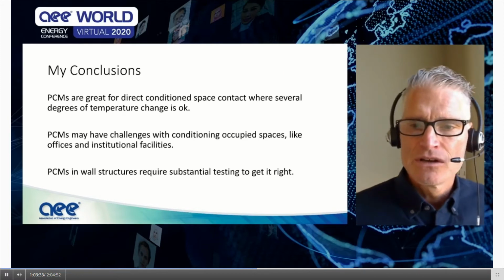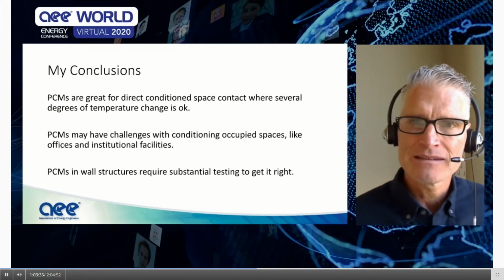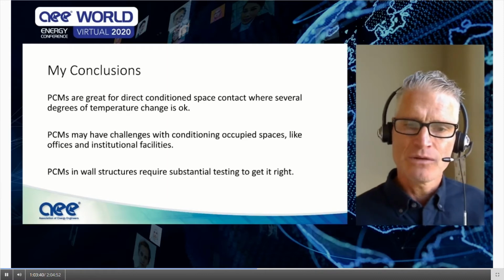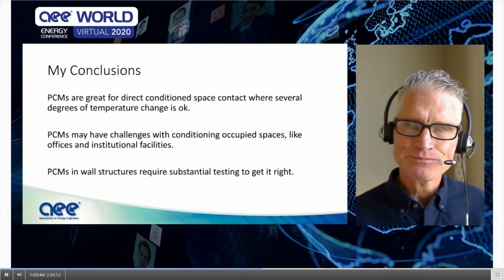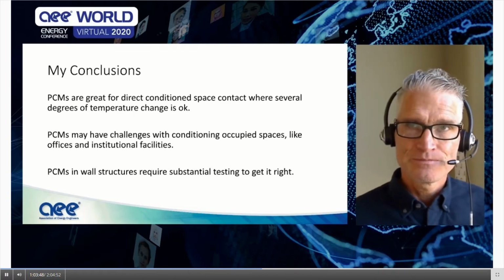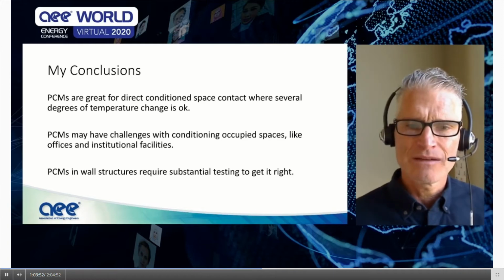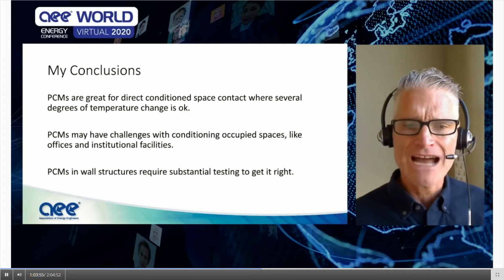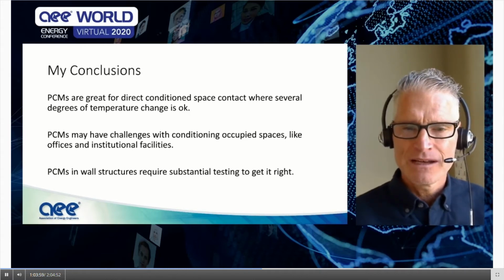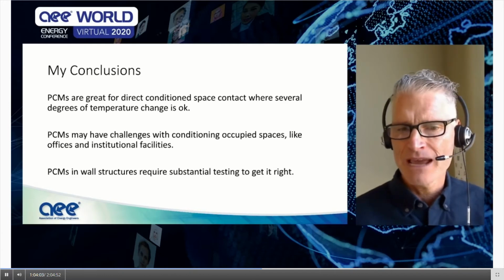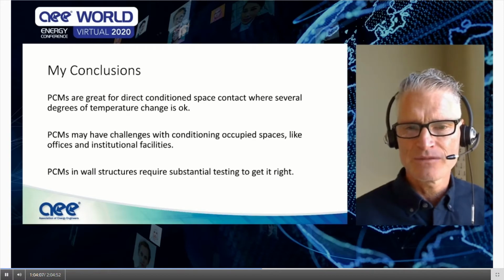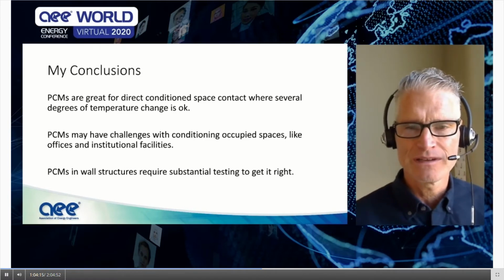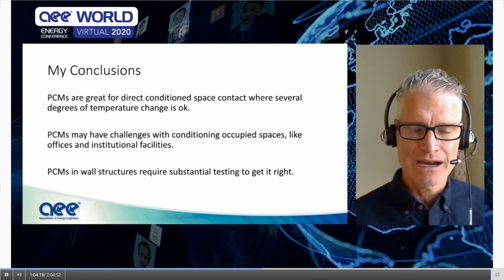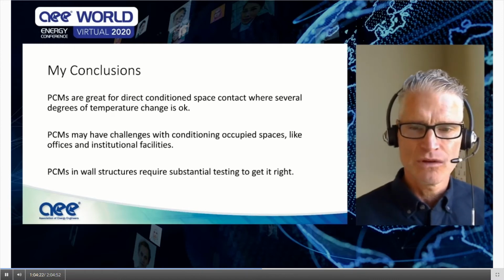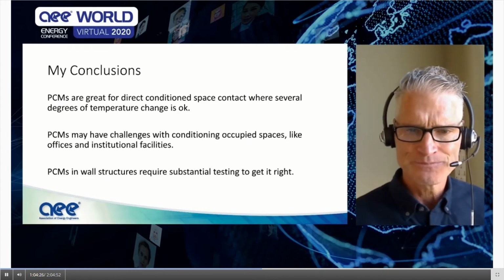PCMs will have challenges cooling or conditioning occupied spaces, again because they need to freeze and melt over a temperature range that's typically not attractive for building occupants. One thing I forgot to mention is that to freeze the PCM when it's installed in a panel or wall, you may have to subcool the space to freeze the material to coast through the day, and that may make the space too cool for occupancy first thing in the morning. You don't want to freeze the material overnight and then have to add heat in the morning because it's too cold for occupants. That's another challenge with that application.